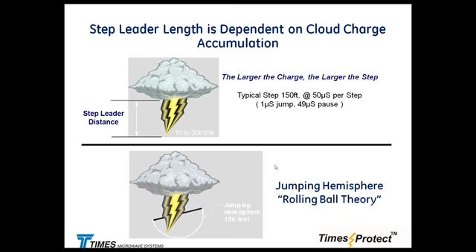So how does the current look like? We know it's going to be short in duration, anywhere from 20 to 30 microseconds. If you look at the lightning current signature, there are a couple of values. There's the rate of rise time - how quickly that current goes from 0, simplified, we mark that at 10% because we're allowing for that 10% to be step potential rise where current doesn't flow yet, up to 90%. So the actual rate of rise time is measured from 10% up to 90% of the current wave shape.